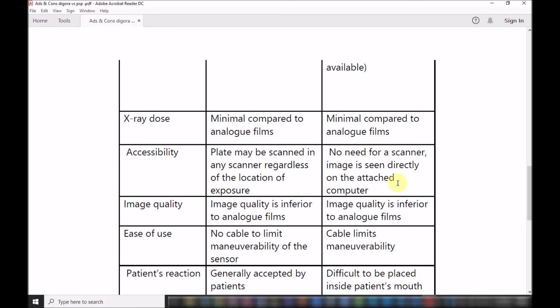Accessibility: plates may be scanned by any scanner regardless of the location of the exposure. As I said earlier, you take the x-ray and then you go back to a scanner which might be remotely placed away from the x-ray machine. With the direct type, you don't need a scanner. The image is directly seen on the attached computer. So when it comes to time management, the direct type is definitely faster because the intermediate step of processing and taking the x-ray and then processing in a scanner is eliminated, and this of course takes time.